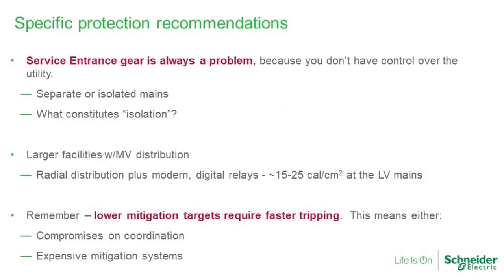Remember, lower mitigation targets require ever faster tripping. And so that means, if you're really trying to get aggressive and trying to get down to 1.2 calories or less than 2 calories or whatever, either you're going to have to compromise on selective coordination, or you're going to have to look at more and more expensive mitigation systems in order to get down to those levels.